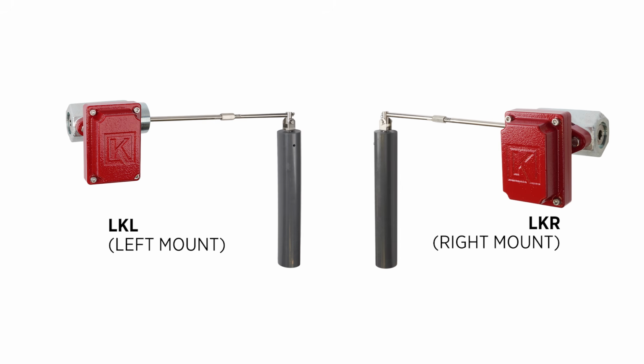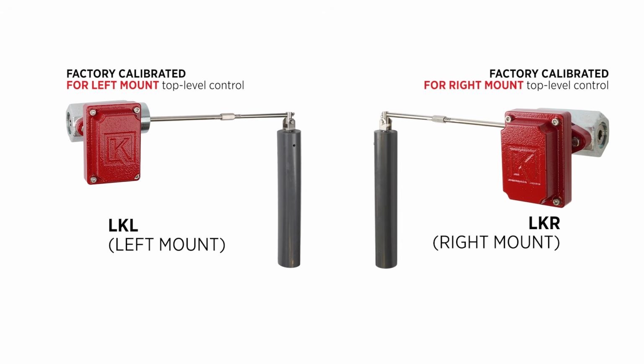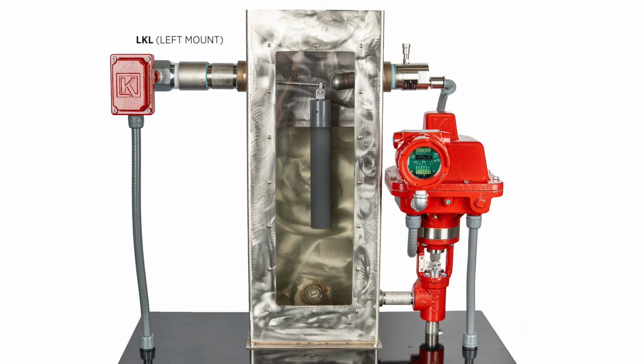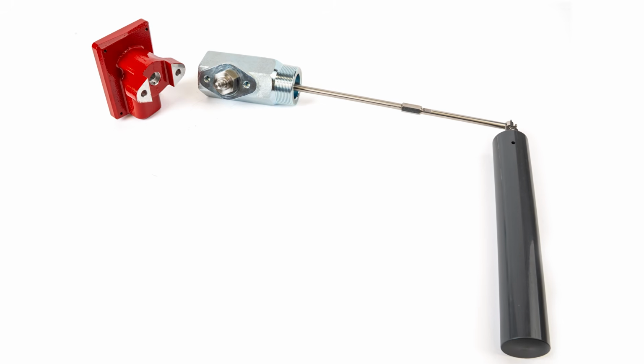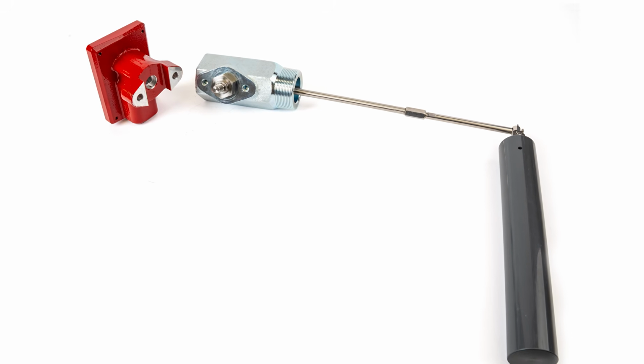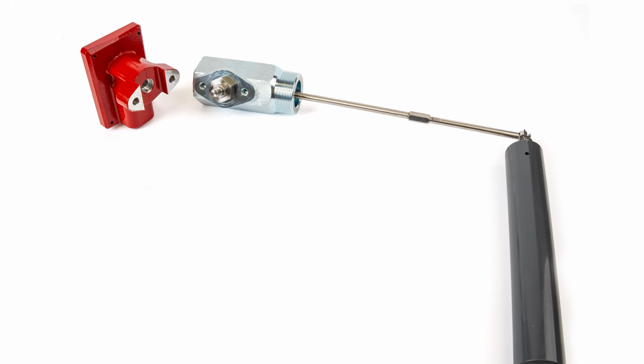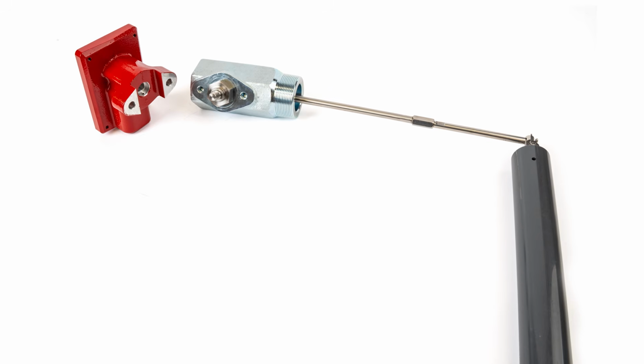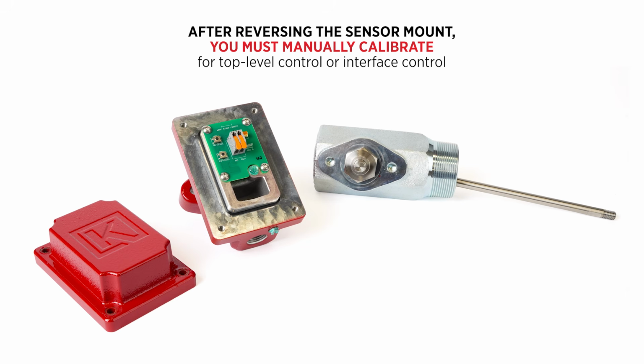The electric level sensor is available to order for left or right hand mount, and each one is factory calibrated for the intended setup. A left hand mount means that when you're facing the sensor, it is mounted on the left side of the vessel. However, it is also field reversible, and the orientation can be swapped if the wrong one was ordered or the setup changes. An important note about this is that you will need to calibrate the unit after reversing the mount.